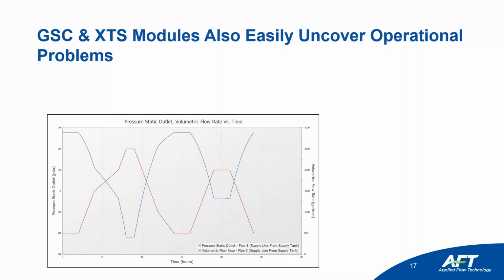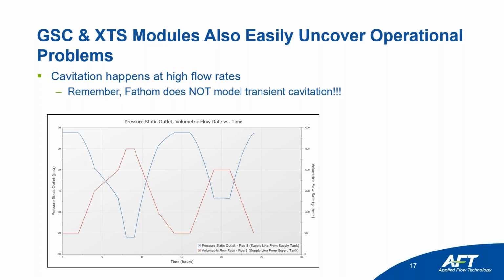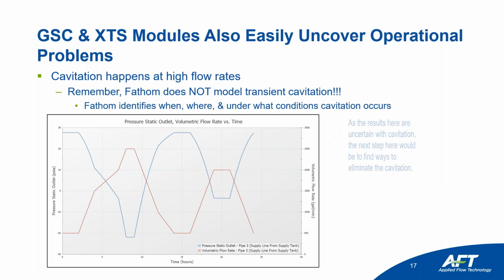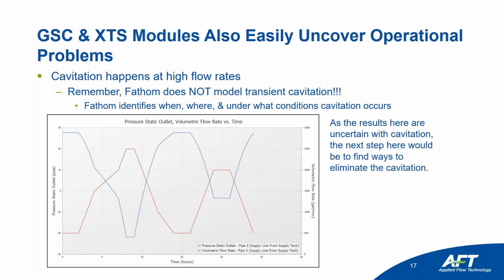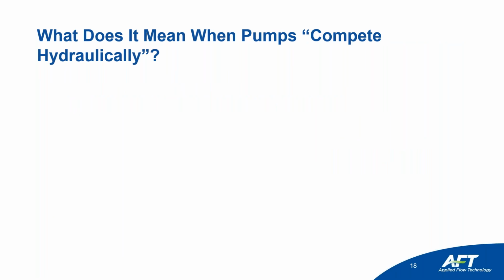Major problems. So they're not related to energy costs, but it just goes to show if you did a good flow analysis, it would uncover an operational problem in a very unintuitive place. So when you're dealing with AFT Fathom, you'll see cavitation can happen at high flow rates. So as that flow rate increases at that flow junction, your velocity increases, and that's where you cavitate. Fathom does not model transient cavitation. It simply identifies where it's happening. So your goal would be to figure out ways to eliminate the cavitation. So this is the advantage of having a good flow analysis.